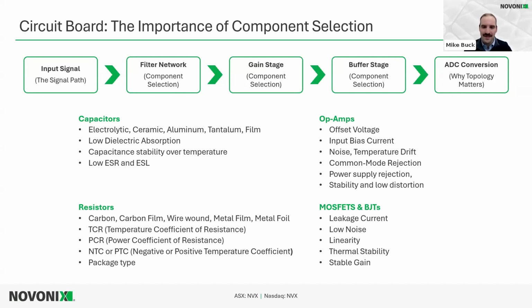I'll touch a little bit on op amps. A few things that you need to look at with op amps: they're something that we use to set up the gain stage and the buffer stage, which is the primary stage before the signal gets to the analog to digital converter. Now, there's a lot of different types and thousands to choose from, but the main thing you have to look into with these is how the offset is going to affect the measurement. This ties into what Stephen was saying about the different slippage factors. If offsets are off or there are biases at the front end circuit level, your data analysis on the cell level is going to be affected. So we want to minimize these noise sources and these offsets as much as possible by selecting high quality components.